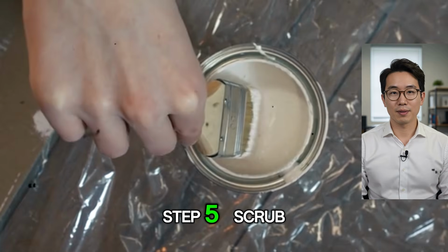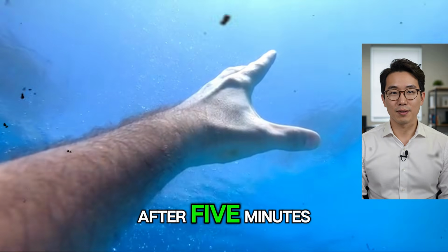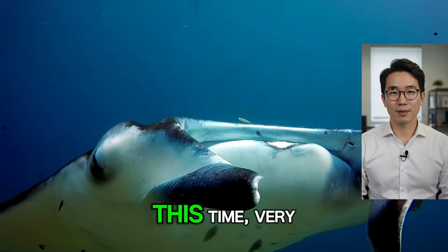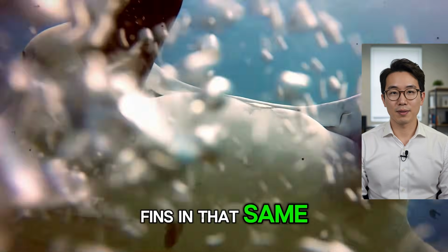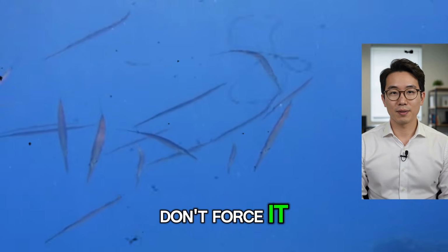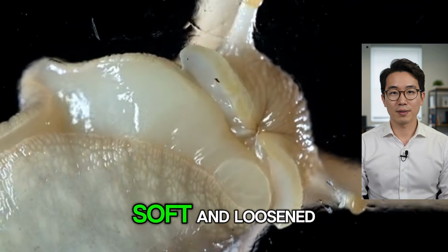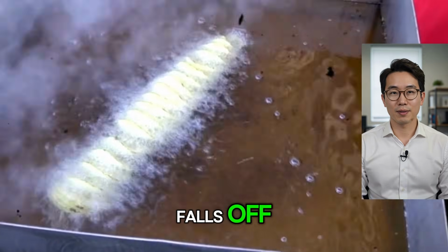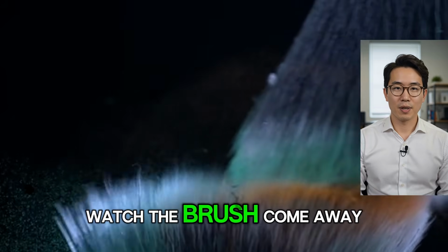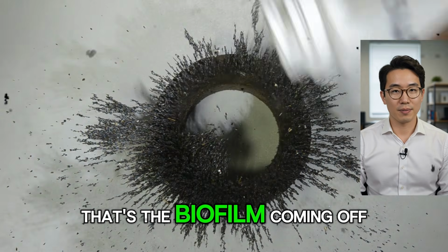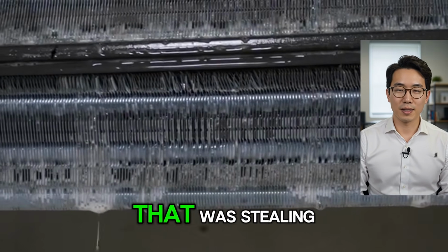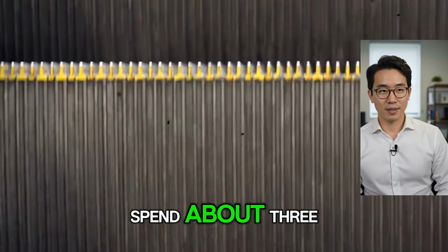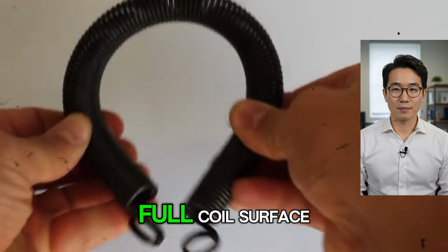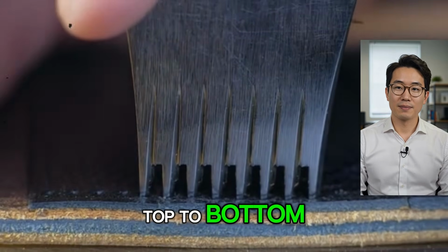Step 5. Scrub gently. After 5 minutes, take your brush again. This time, very gently, scrub the fins in that same downward direction. Don't force it. You'll notice the grime is already soft and loosened. It practically falls off. Can you see that? Watch the brush come away dark. That's the biofilm coming off the fins. That's the buildup that was stealing your cooling power. Spend about 3 to 4 minutes here. Work across the full coil surface, top to bottom.